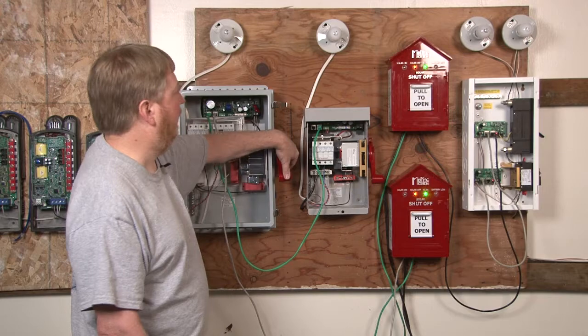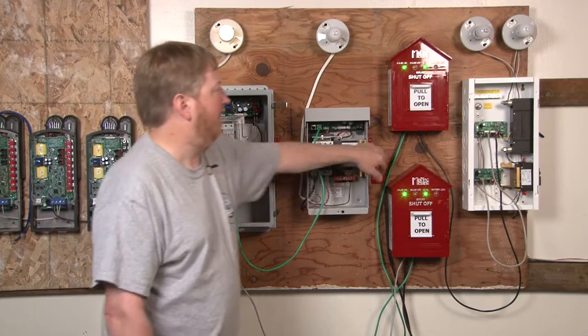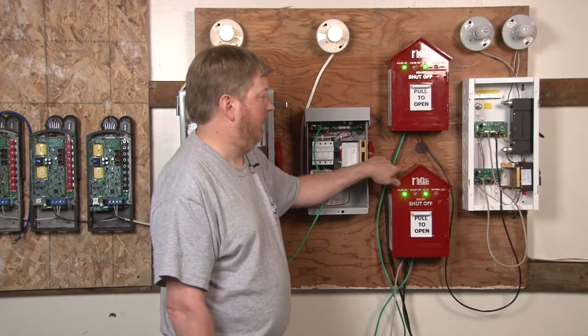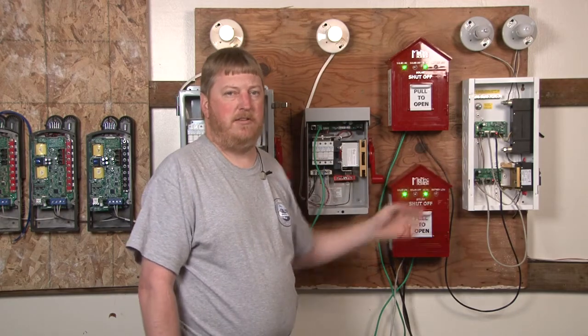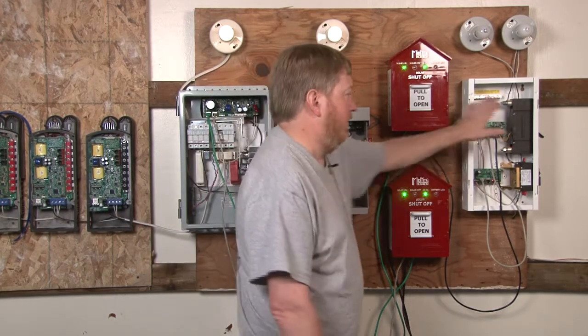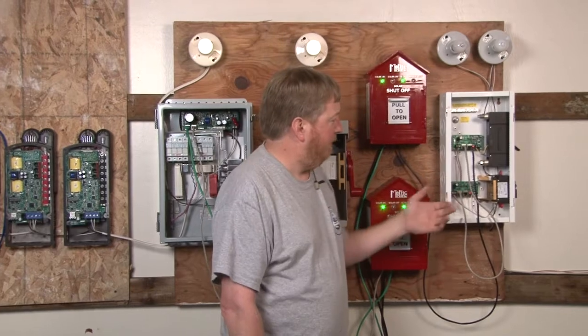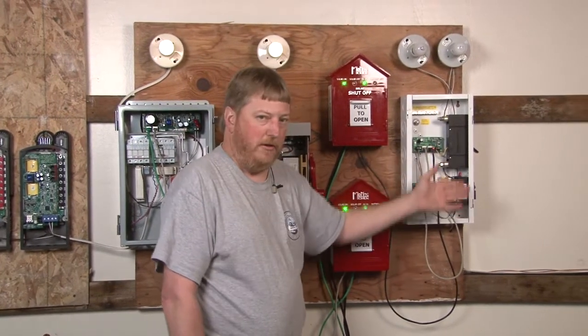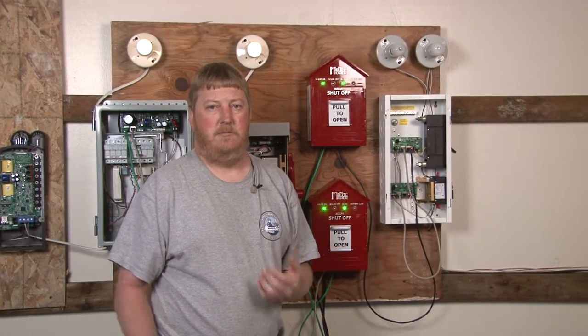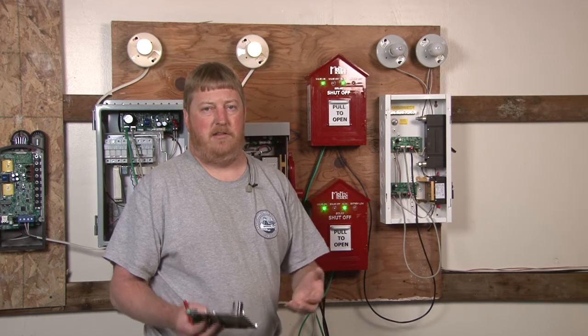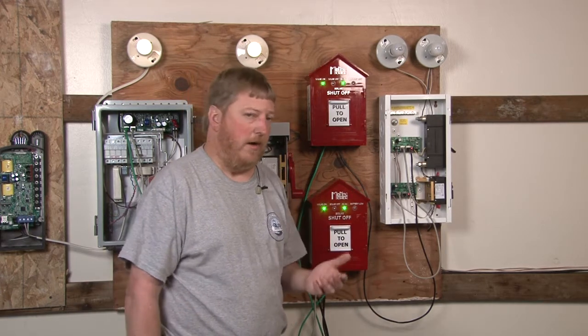Okay, I'm going to turn it back on again, one more time. The combiner circuit breaker is closed. Now I'm going to talk a little bit about the battery disconnect modules. This box over here is an example of a system. Basically, this would only be used when there's batteries in a system, be it battery backed up grid tie, AC coupled with batteries, or off grid.